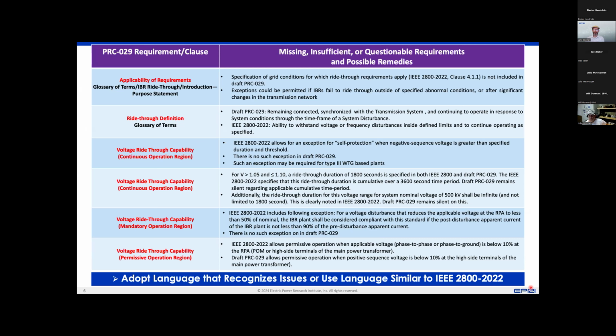We will not have the time to go into all of those details, but on the first slide, we will review missing or insufficient or questionable requirements and possible remedies in the most recent draft of PRC 29. In the next slide, we will look at internal inconsistencies that we still see in the draft. And that draft was published, I think, on Tuesday last week. And then on the third slide, we will highlight specific areas where the current draft appears to conflict or go far beyond the IEEE 2800 requirements. So let's pick a few examples here.